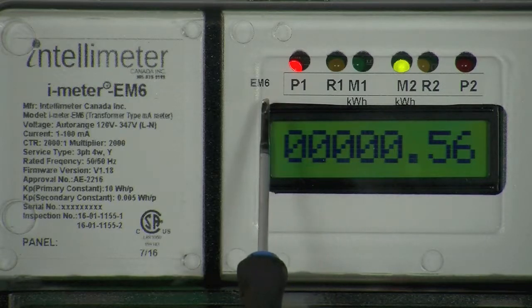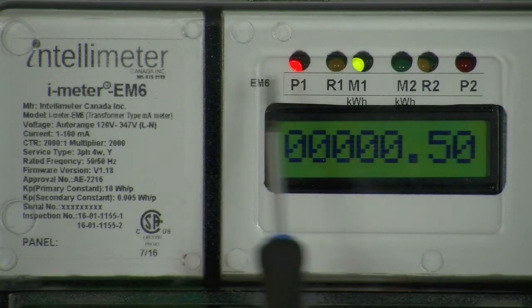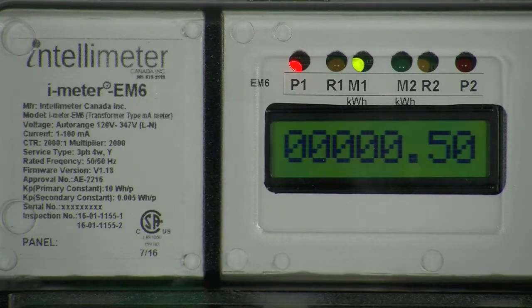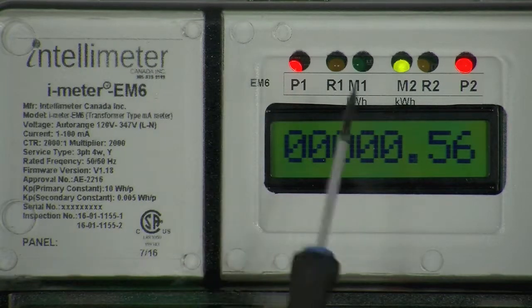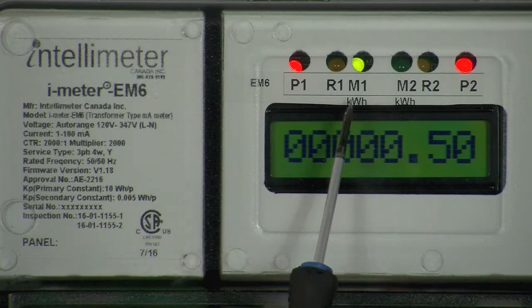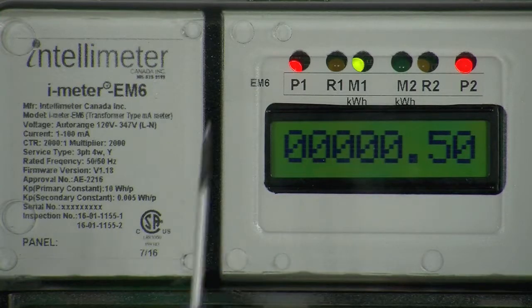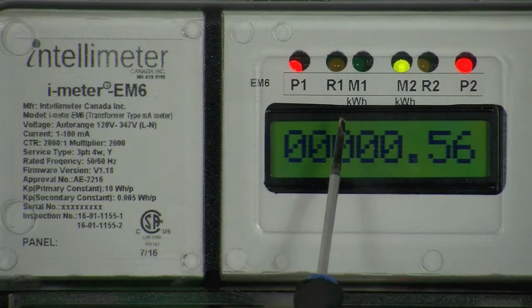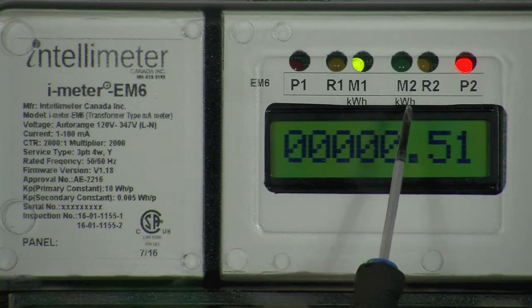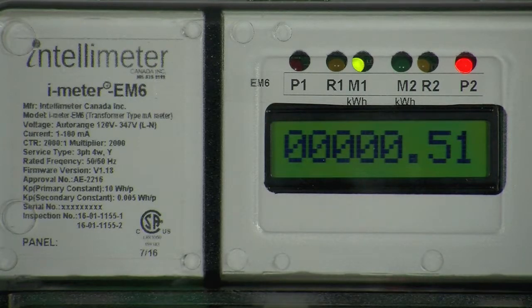So the first and last red blinking LEDs marked P1 and P2 are pulse indicators. These LEDs will pulse faster depending on how much load is on the system. The two green LEDs marked M1 kWh and M2 kWh indicate which meter number is being displayed at that given time. When the M1 light is on, kilowatt hours for meter 1 are being displayed, and when the M2 light is on, kilowatt hours for meter 2 are being displayed.